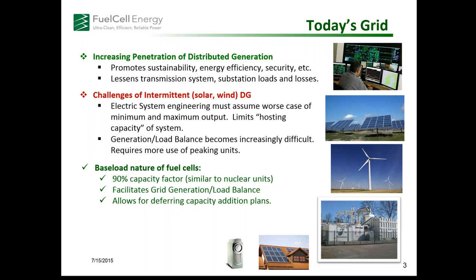So looking at fuel cells as distributed generation, we have a very high capacity factor, similar to baseload nuclear units and gas turbine or coal units at central power plants, with all the benefits Andy talked about. That facilitates grid generation-load balance because we have constant power output, and it allows the utility to make plans around the benefit of lessening loads on the system. They really can't take credit for that if it's not firm or baseload power. So it allows for maybe deferring a substation upgrade, or in larger amounts, it could defer transmission system upgrades, which are very difficult to implement.